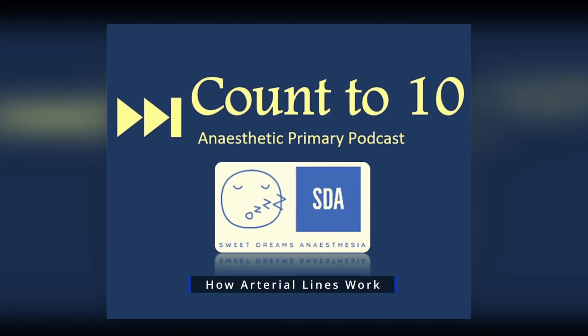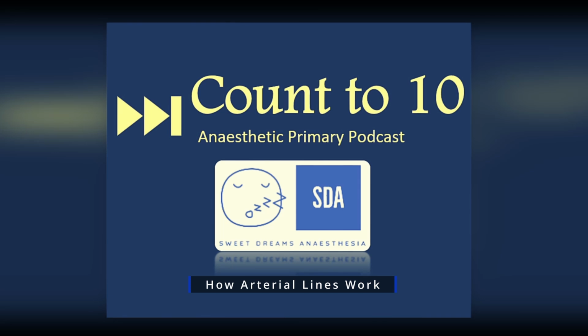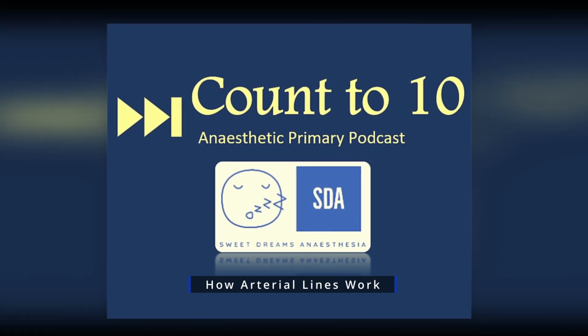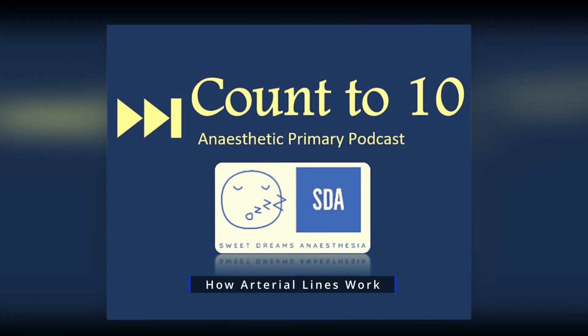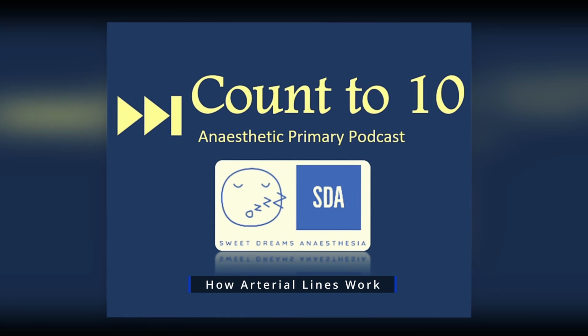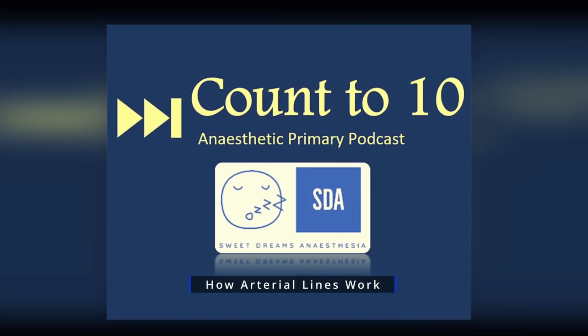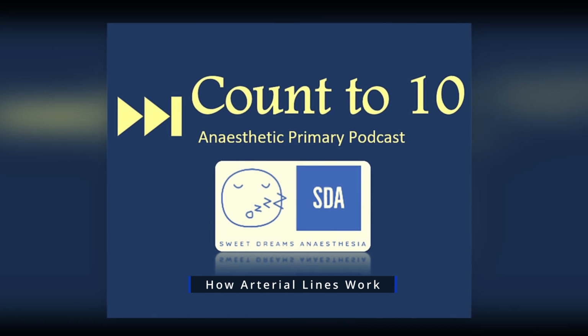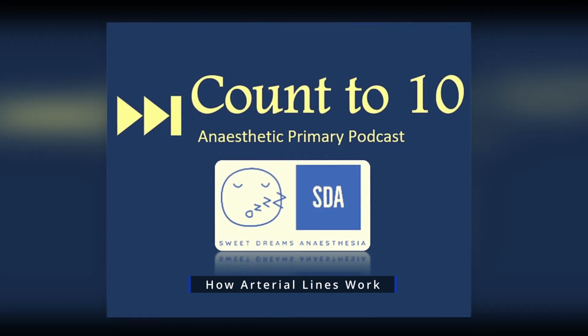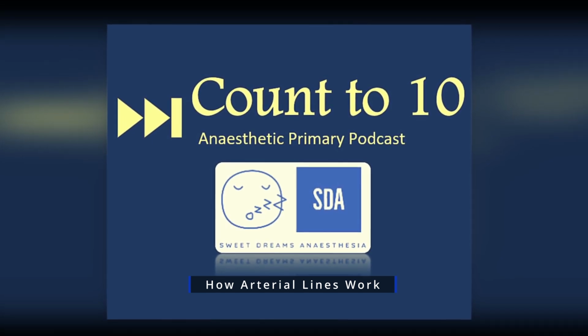That strain gauge is incorporated into an electrical circuit, and when that strain gauge changes its shape, it changes the resistance within that electrical circuit. This therefore allows an initial pressure energy to be converted into an electrical energy via change in resistance. Now normally, this strain gauge was part of a bigger electrical circuit called a Wheatstone bridge.